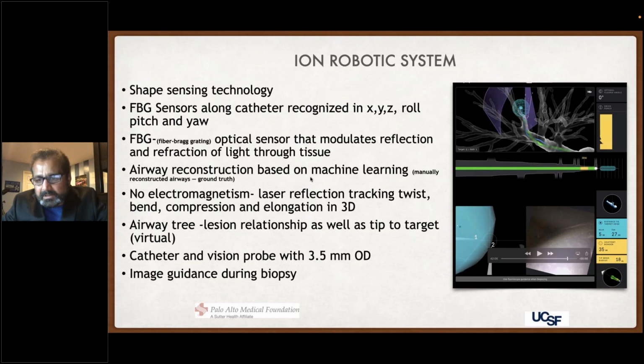So the basic functional unit of the ION robotic system is a fiber Bragg grating sensor, and we'll talk about more of what that is. The sensors are along the catheter in its entire length, and it's recognized in XYZ, roll, pitch, and yaw, especially the tip. So it has the characteristics of navigation there. The fiber Bragg grating optical sensor uses a laser, a monochromatic sweep laser, that actually travels through the length, and the reflection and refraction are picked up. And we'll talk about it in the next slide. The airway reconstruction algorithm is also different as opposed to all the previous generations of peripheral navigation platforms.